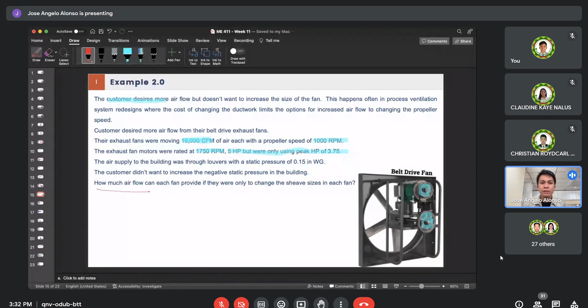Okay. Then what will be the effect of that increase on our new flow rate? This is what is asked in the problem. How much airflow can each fan provide? So from the original 15,000 cubic feet per minute, we increase the RPM by 10%, to 1,100 RPM. Then what will be the effect on the fan capacity? Based on our fan affinity law, class, that is just directly proportional. Q1 over Q2 equals N1 over N2. Since it is directly proportional, we will also have a direct 10% increase in our fan capacity. Okay? So from 15,000, our fan capacity increased to 16,500 CFM.